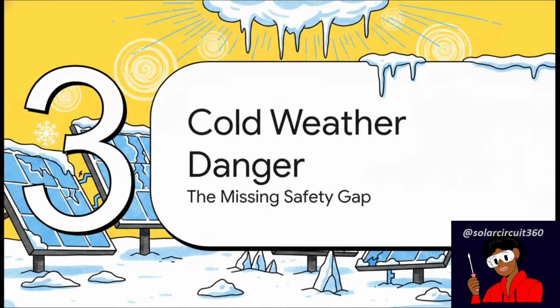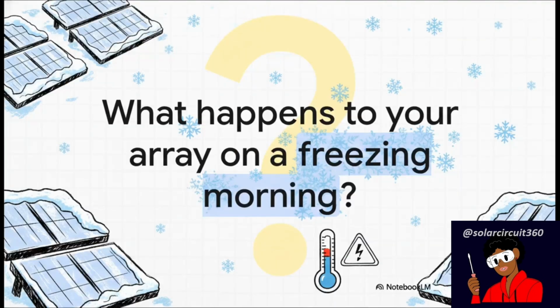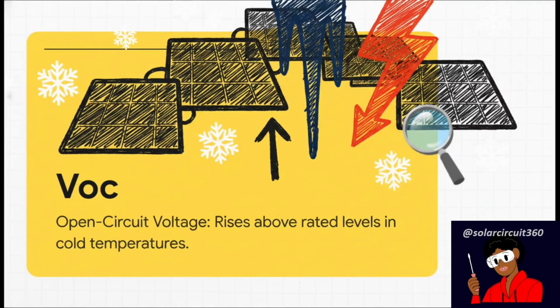Let's move on to section 3, the cold weather danger. So, what actually happens to your array on a freezing winter morning? A lot of installers will size their solar strings using standard data for a nice sunny summer day. But as our source points out, doing that leaves a massive hidden danger just waiting for the temperature to drop. The real culprit here is Voc, or open circuit voltage. That's the voltage of a solar panel when it isn't connected to a load.